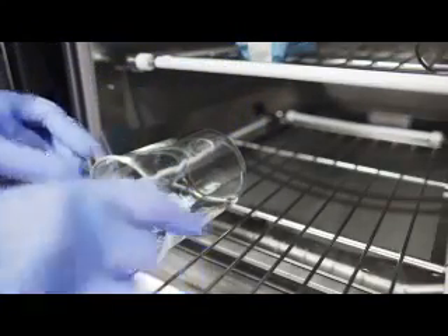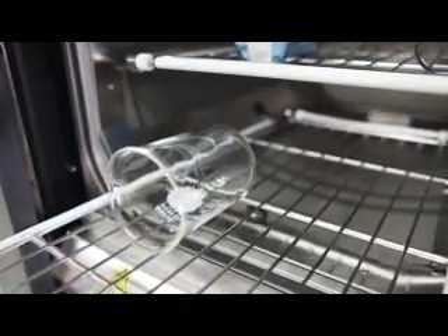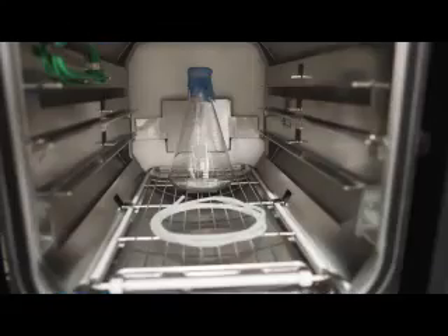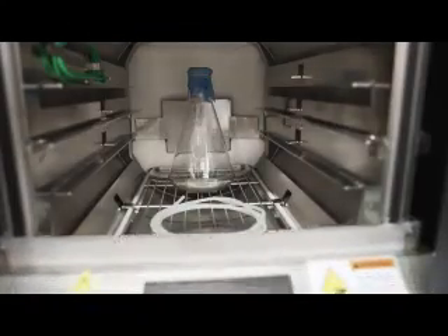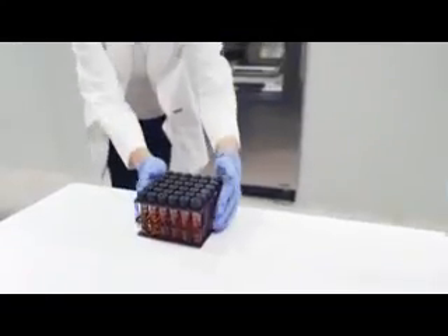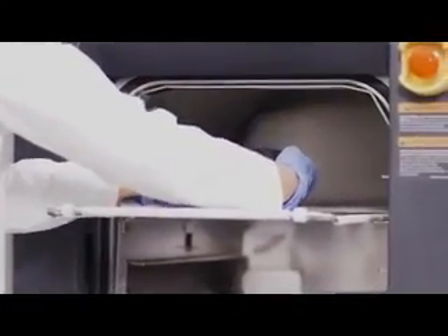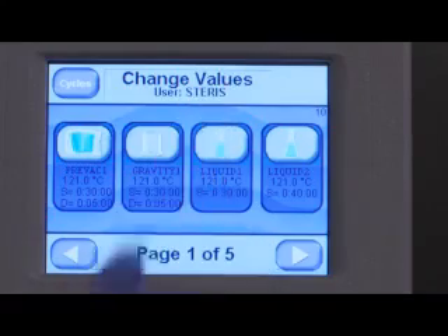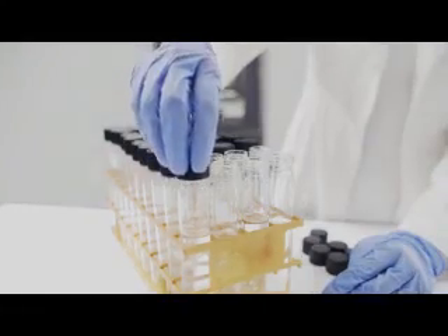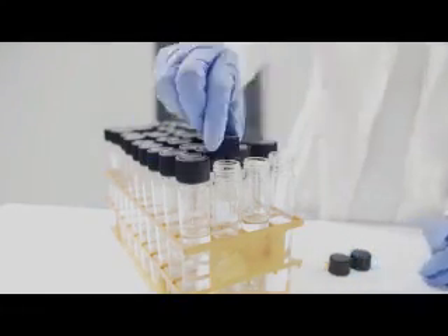Look for any items that might trap air. For tubing or glassware that cannot be inverted, it is also important to utilize a pre-vacuum cycle. It is very important when sterilizing liquids to utilize a liquid cycle. When sterilizing liquids, you must only use open or vented containers to avoid the risk of rupturing from internal pressure.